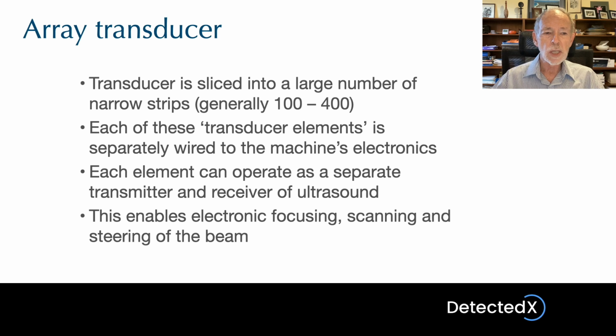The reason this is useful is because the slicing up of the transducer means that these transducer elements can actually act as independent small transmitters and receivers of ultrasound. In the previous talk, I said this is exactly what we need in order to focus. So the cutting up of the array transducer into a large number of elements like this means that it can be used for electronic focusing of the ultrasound beam. It also enables the scanning of the beam and the steering of the beam, in other words, pointing it in other directions when this is needed.